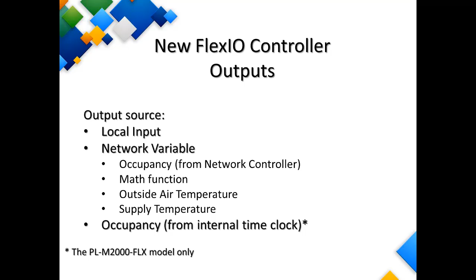So what kind of logics can we put? Well, obviously, this being a flexible I/O controller, we can choose what we want our outputs to do. So what are the logics? Is it a heating logic or cooling logic, or direct acting, reverse acting? And what are some of the different kinds of actions it can do? Well, obviously it can be on-off. It can be a modulated signal, and we can also do pulse width modulation for the digital outputs as well.